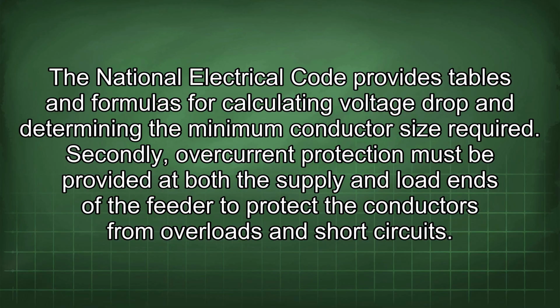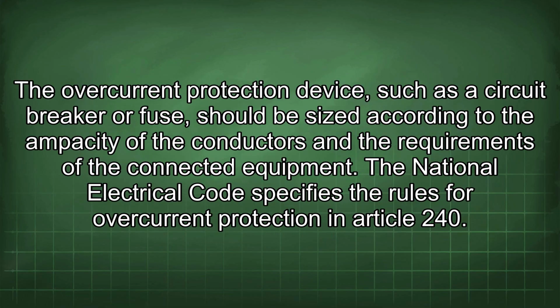Secondly, overcurrent protection must be provided at both the supply and load ends of the feeder to protect the conductors from overloads and short circuits. The overcurrent protection device, such as the circuit breaker or fuse, should be sized according to the ampacity of the conductors and the requirements of the connected equipment. The National Electrical Code specifies the rules for overcurrent protection in Article 240.